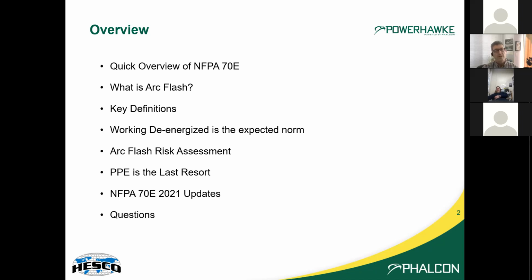One of the other bigger changes is the updated IEEE 1584 standard that came out in 2018, which impacts the calculations of incident energy when doing arc flash analysis. The importance there, for most end users, is this IEEE update has the potential to impact the scope of work that an engineer will define for you when doing these assessments. That's sort of the highlights of what's in store in this next version of NFPA 70E.